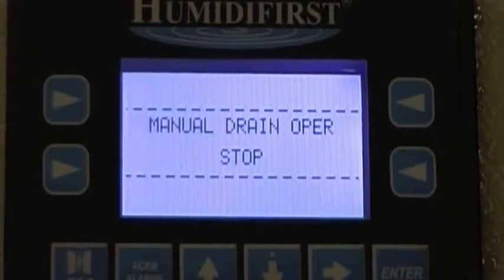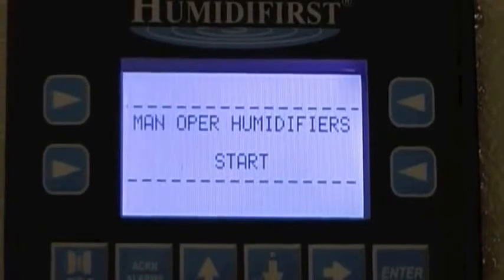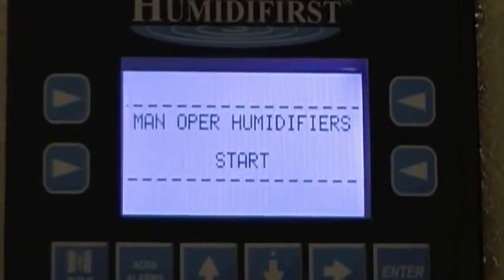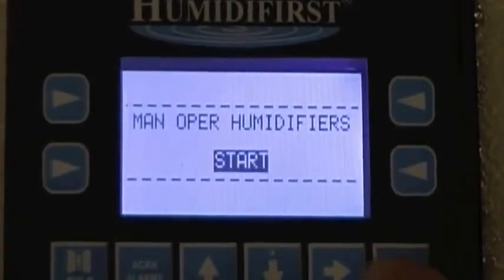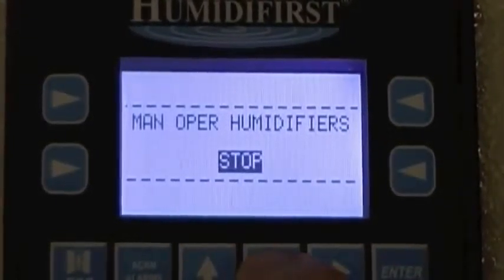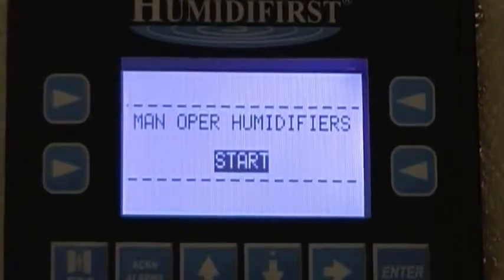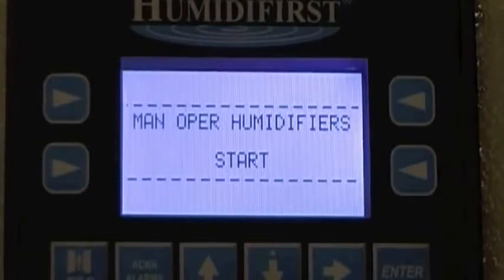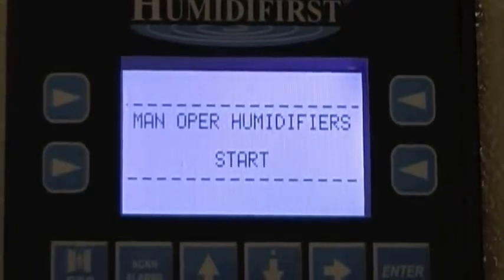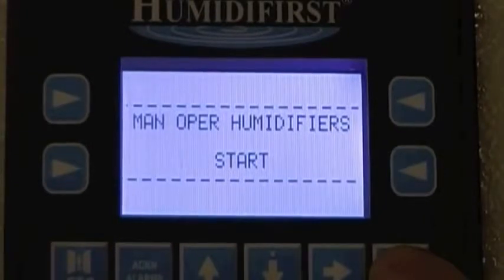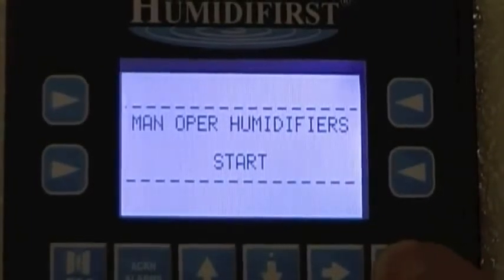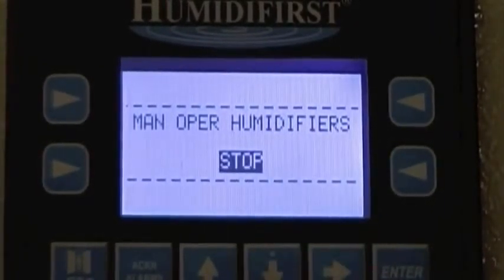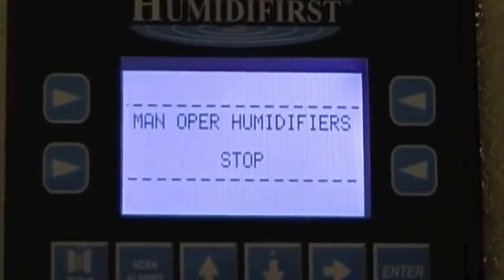Button number 9 is manual operation of the humidifiers. Pressing button number 9 will allow you to run your humidifiers in manual operation no matter the BMS signal. In the manual operation screen, you will press Enter to highlight Start and Stop. Set it to Start and press Enter. Your manual operation is now engaged. Your humidifiers will run at a factory setting of 10 minutes. To stop manual operation, you may hit Enter, scroll to Stop, and press Enter again. This will stop your manual operation.